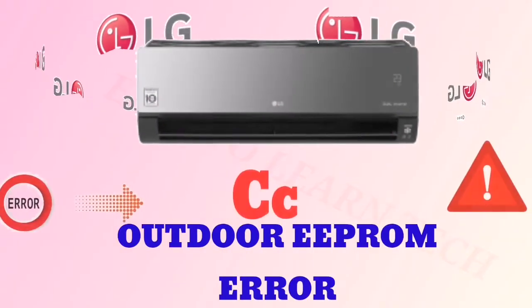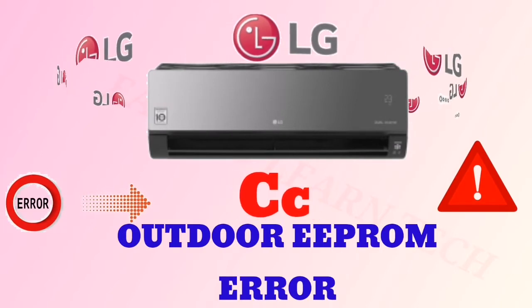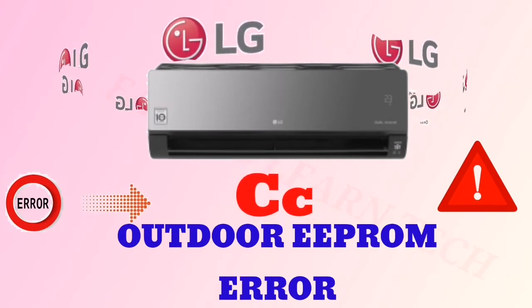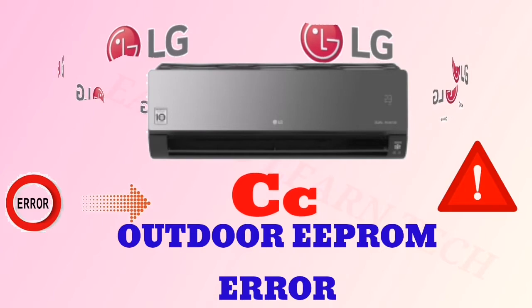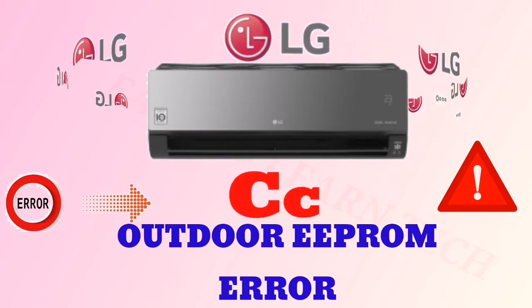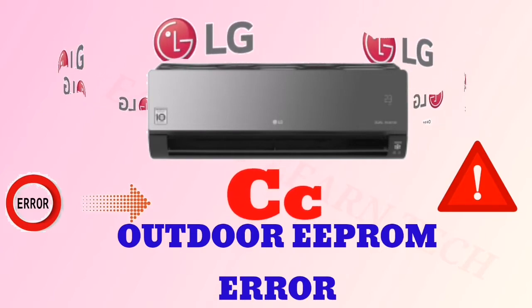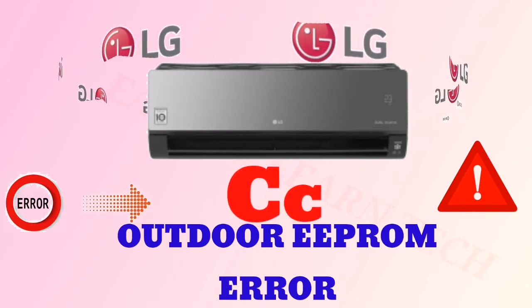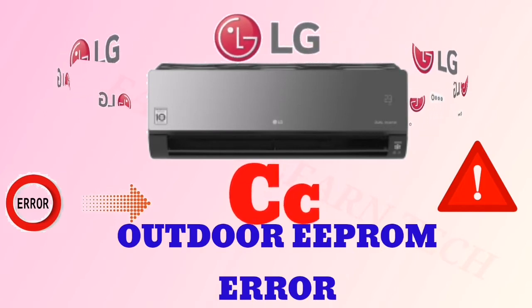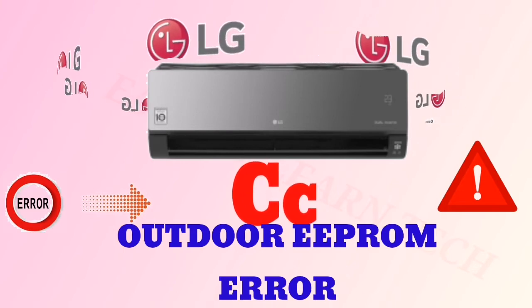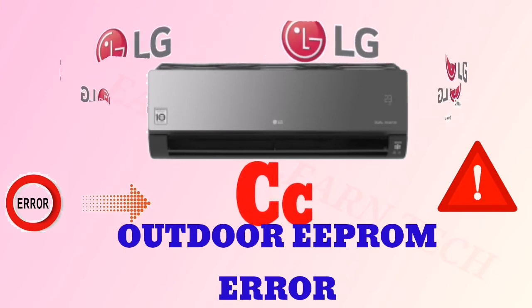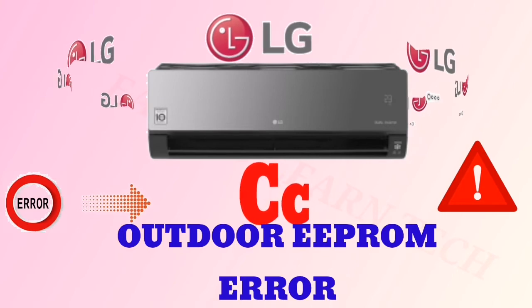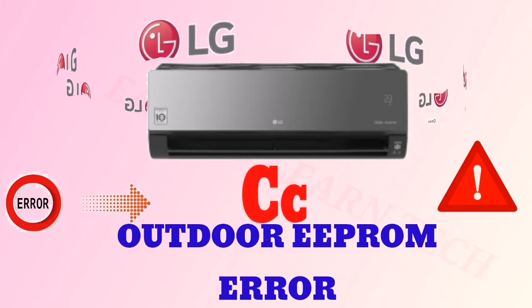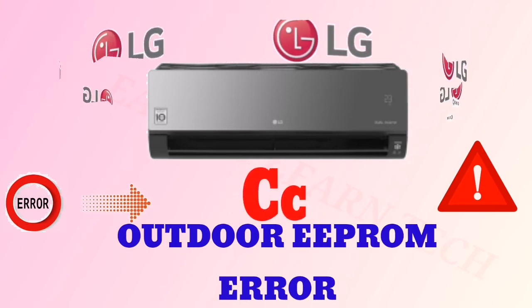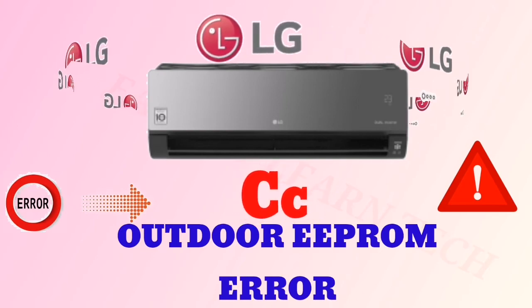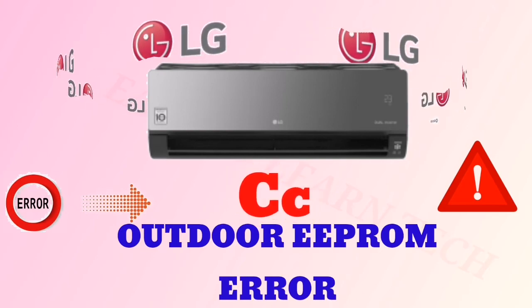Let's see the next error code. When you see the error CC, it means outdoor EEPROM error. At that time, first of all, you have to check whether the PCB has been burned due to electricity fluctuation or any other causes. If your PCB is not burned, then you have to put in a new EEPROM and start the unit. And if the error doesn't occur again, it means it was the fault of the EEPROM. You can get this EEPROM from the company, install it and start the unit. It will be working. If it doesn't work, then you have to change the outdoor PCB. Your unit will be in working condition.